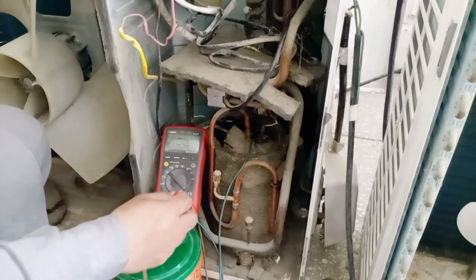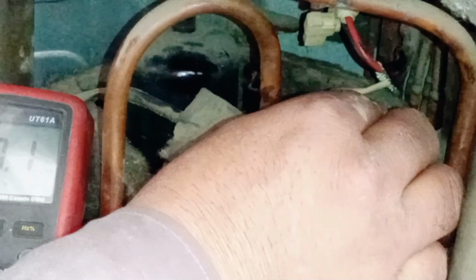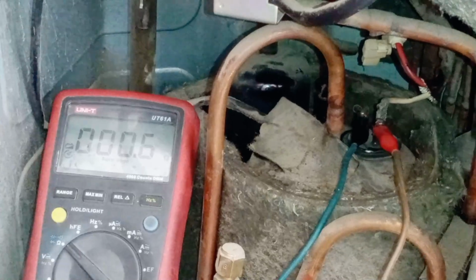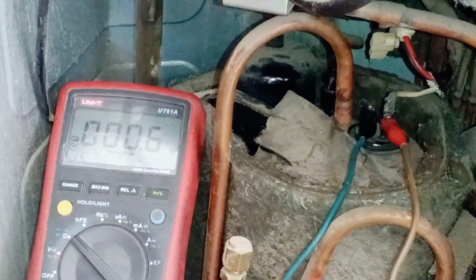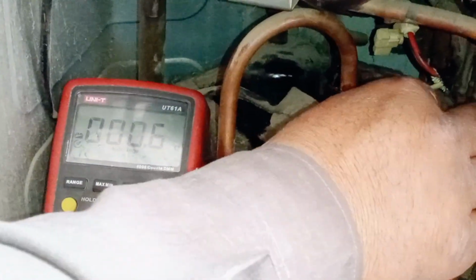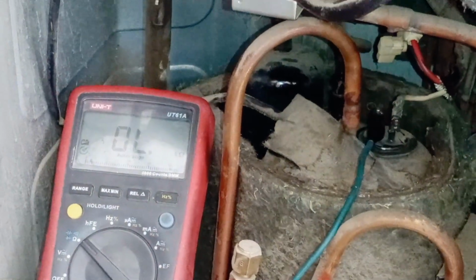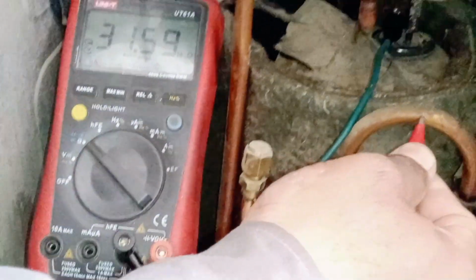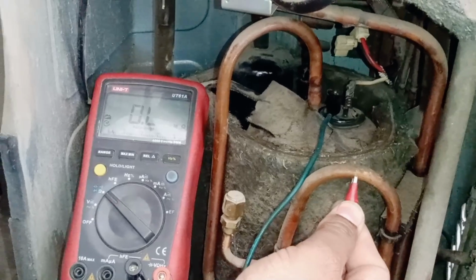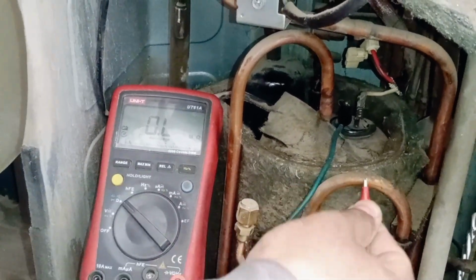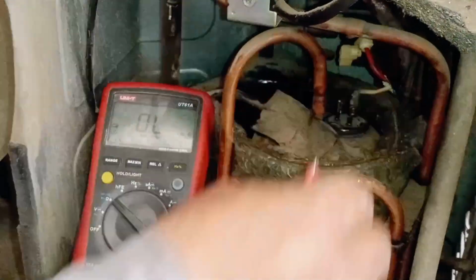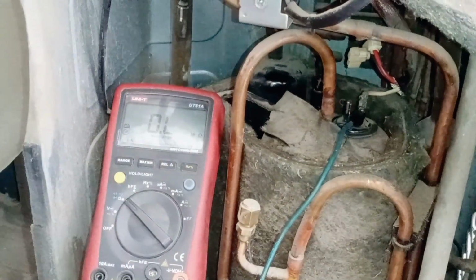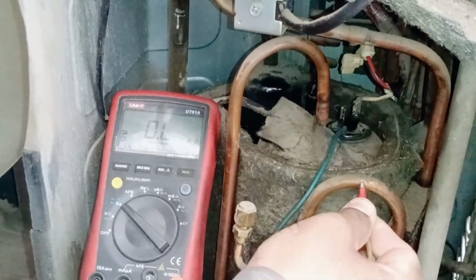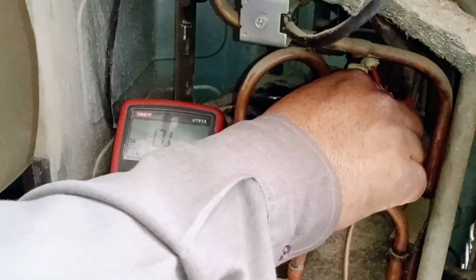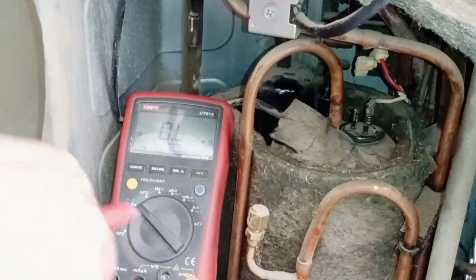Now, let's test the second compressor. Let's check the resistance value of this compressor winding. And here we go. It reads 0.6 ohms, the same as the previous compressor. All terminals show the same value, indicating that the compressor winding is fine. However, when performing the body short test, the resistance value shows up for a few seconds and then disappears. And on attaching the probe back with the copper pipe, no value is shown. I'll shift the black probe to another terminal and place the red probe on the copper pipe. There's no value showing now. We'll need to wait a bit since the previously shown resistance has disappeared.